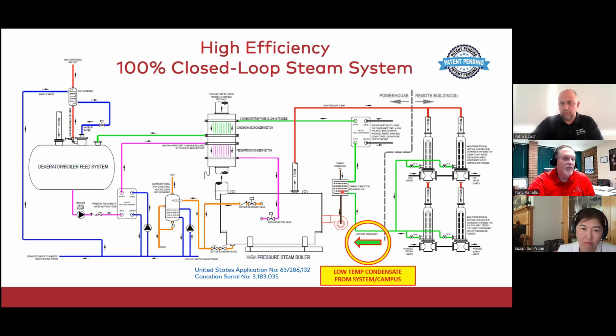Once we do that and we preheat our combustion air, we reject some of that heat to other heat sinks like makeup water or domestic hot water preheat, and we can get our condensate back to the condensing portion of our economizer low enough, we can condense the condensate back before it goes back to the deaerator.